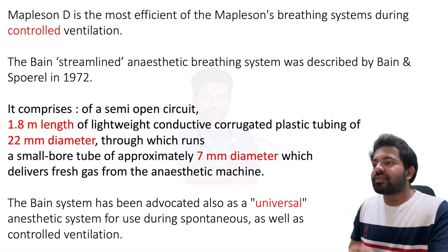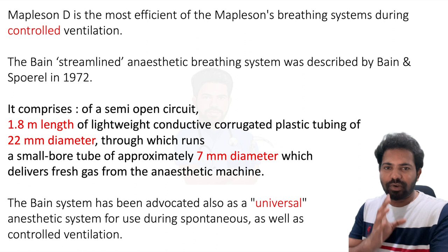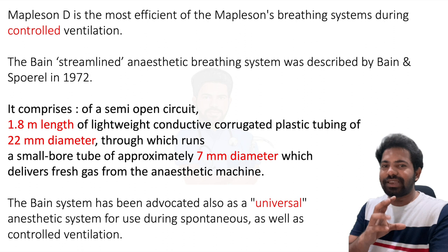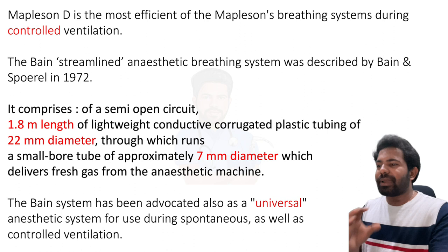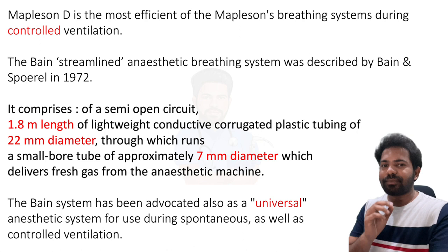The Bain circuit comprises a semi-open circuit. It is 1.8 meters or 180 centimeters in length. It is a lightweight, portable, conductive, corrugated plastic tubing with a 22 mm diameter outer tube which is transparent. It also has a small bore 7 mm diameter inner tube which delivers the fresh gas flow from the anesthetic machine to the patient. The Bain system has been advocated as a universal anesthesia system because it can be used in both spontaneous as well as controlled ventilation.